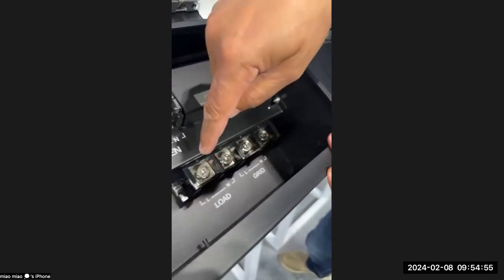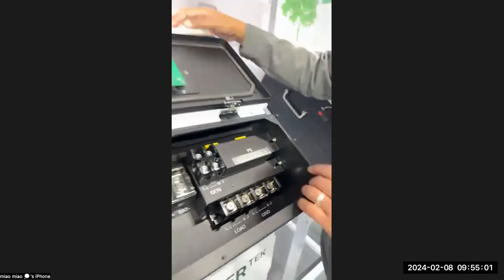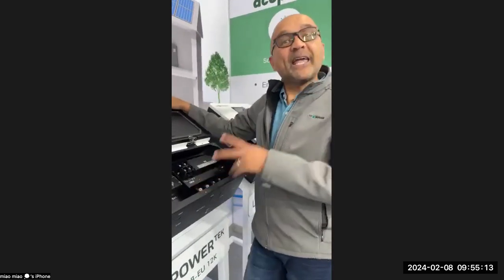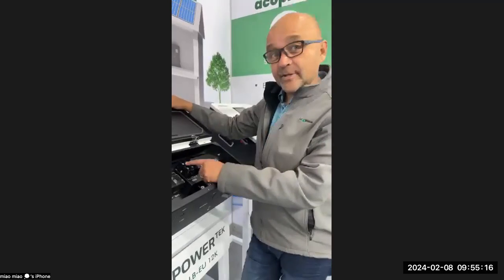And once again, you've got to take care to use the correct lugs and also torque them down correctly. And you must remember that earlier on, I said to you that the 12 and the 10 have a smart load function. So what does that mean? We've heard guys talk about our competitors having an auxiliary port. Well, did you know that this machine can do that as well? And how do we do it? We do it through the same port.